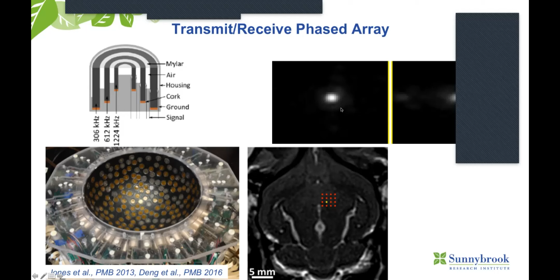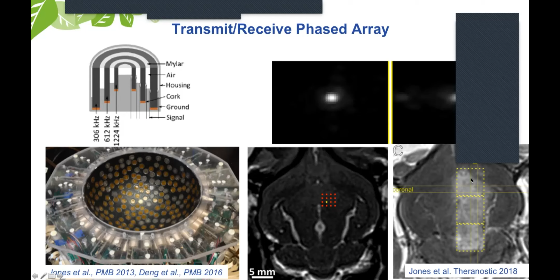And how can we do that? So the first thing is we need to get rid of the MR scanner. We need to be able to do the imaging with the same device that we are treating with, the ultrasound. Here is an experimental array where we have these ultrasound sources that can also listen to the sound. So we transmit and we listen. Here is a preclinical model where we were sonicating in this grid. And when we sonicate in that location, we captured all the data. And here you can see the image of those bubble vibrations in vivo, in the actual blood vessels, showing where things are. So now we can localize where things are, to then control the treatments and do it without an MRI scanner.